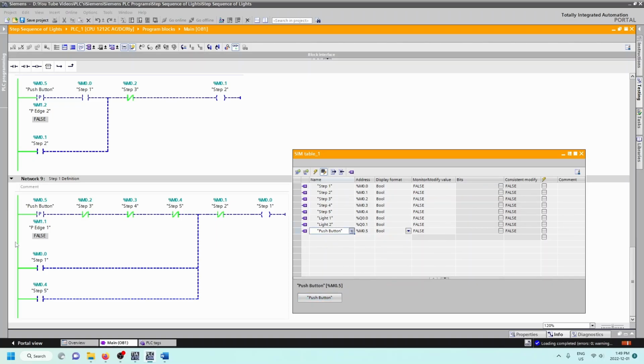Now when I press the push button, this positive edge will only come through, hopefully for one scan cycle, and just keep us in the first step here. So doing that now. Oh, nice. Okay, so step 1 is true. Okay, holding contact, keeping that guy on. Okay, because you'll see that here, this is no longer true. Okay, then we're moving up to this one right here. I will press the push button. This is true. Step 1 has been confirmed.